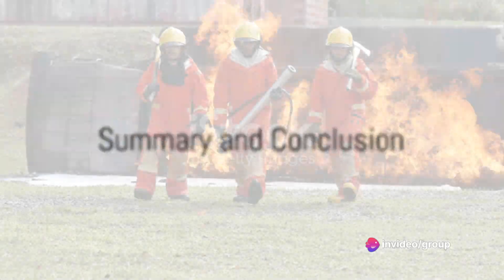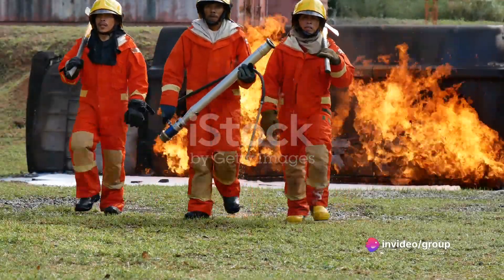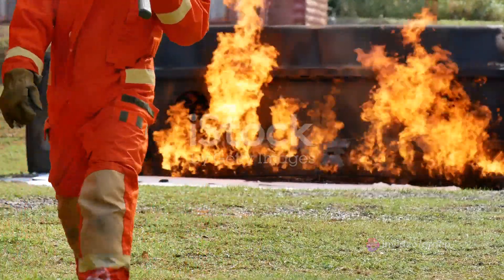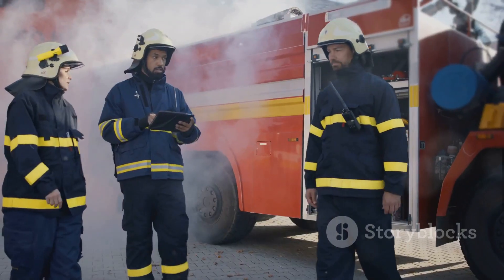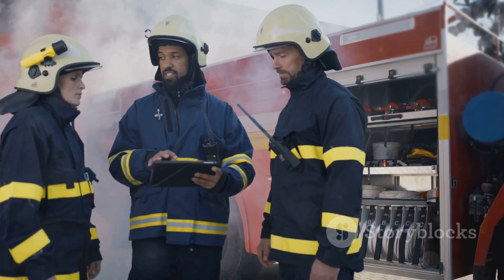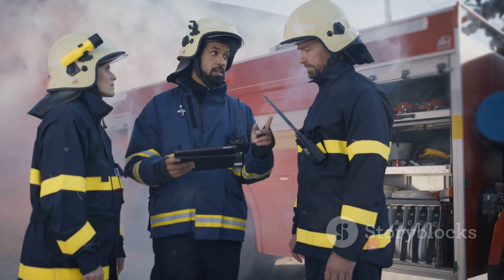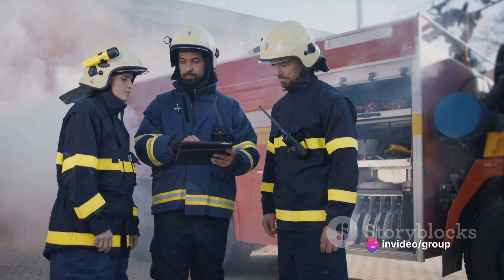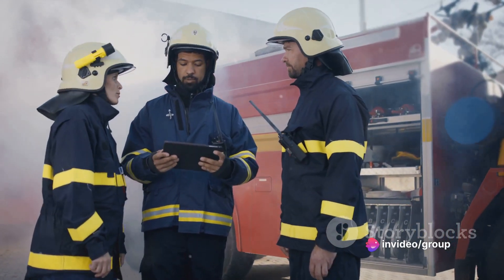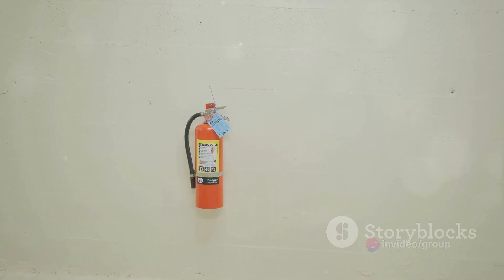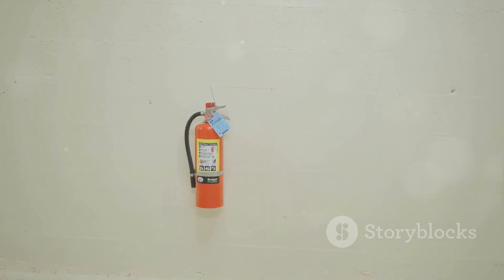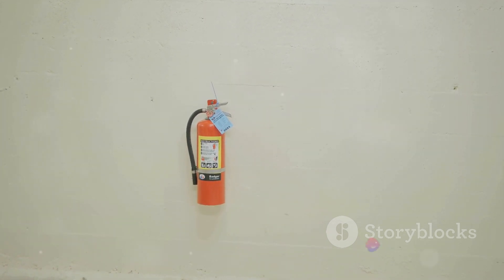In summary, understanding the different types of fires and how to extinguish them is a critical part of fire safety. Class A fires are best extinguished with water or a monoammonium phosphate fire extinguisher; class B fires with a foam fire extinguisher; class C fires with a carbon dioxide or dry chemical fire extinguisher; class D fires with a special class D fire extinguisher; and class K fires with a class K fire extinguisher.